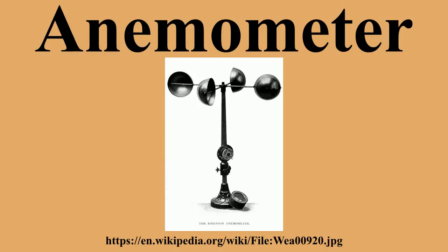Ultrasonic anemometers. Ultrasonic anemometers, first developed in the 1950s, use ultrasonic sound waves to measure wind velocity. They measure wind speed based on the time of flight of sonic pulses between pairs of transducers. Measurements from pairs of transducers can be combined to yield a measurement of velocity in 1, 2, or 3-dimensional flow. The spatial resolution is given by the path length between transducers, which is typically 10 to 20 centimeters.